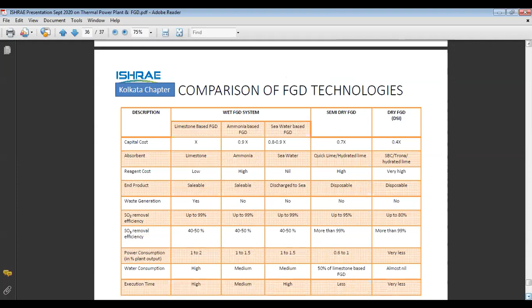This is the comparison of all types of technology. If you compare cost-wise, the capital cost of limestone based WFGD is the highest, X. Ammonia based is 0.9x, and seawater is 0.8 to 0.9x. Semi-dry is 0.7x and dry FGD system is 0.4x. Currently, as per the CEA guidelines, for limestone based WFGD technology the capex is around 50 to 60 lakhs per megawatt for a thermal power station. So accordingly, if you calculate for a 200 megawatt unit, suppose the price is X, then the price of ammonia based and other technologies can be estimated.